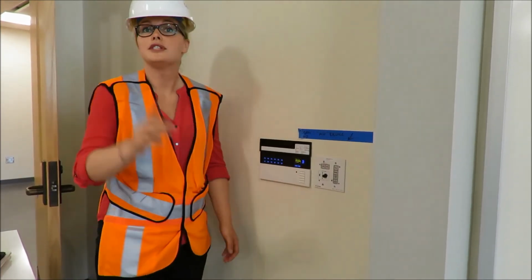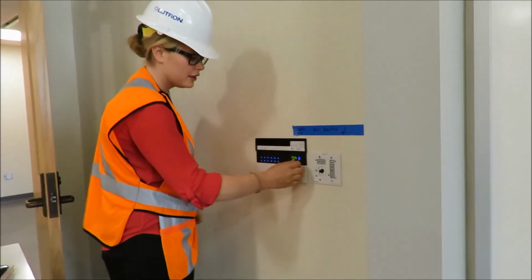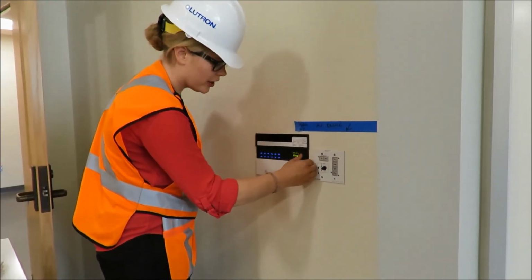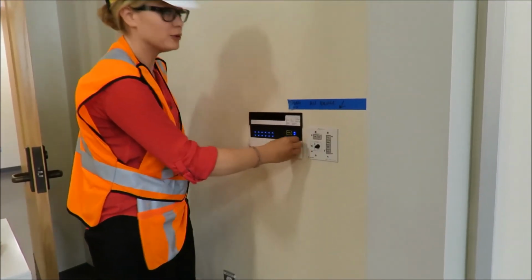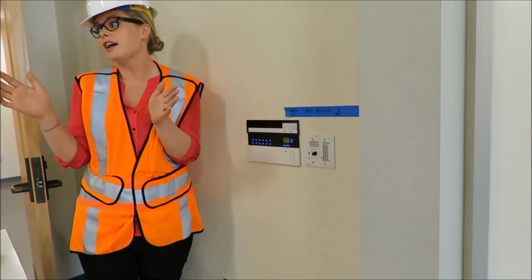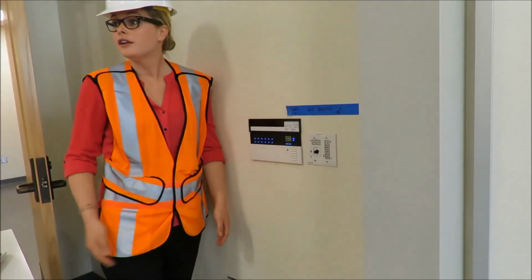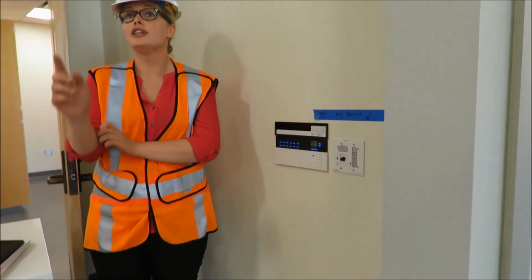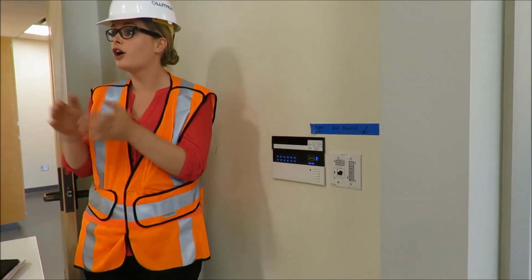Sensor setup, like I was saying, you have an occupancy sensor and a daylight sensor. You can go in and look at setup for daylight, and it will find the sensor and tell you which zone. So if you wanted all of your lights to daylight, you could change it in here. Right now, it's only set to daylight those front 3, but you can change it so that all the lighting daylights.